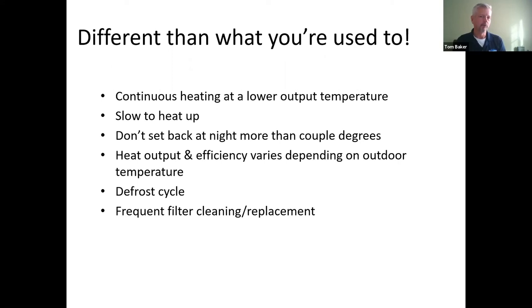So when we got our first heat pump, my wife had a hard time understanding it because she was used to grabbing her coffee on a cold morning, finding her favorite heat register, standing over it, and letting that warm air blow on her. When we got the heat pump, she was convinced something was wrong because she didn't feel that warm heat hitting her legs. So there's a 20, possibly a 20 plus degree temperature differential in the heat coming out of the register. That means it's going to take longer for a heat pump to get your house up to the design temperature. Let's say it's 70 degrees in the wintertime. It'll take longer to get it there.